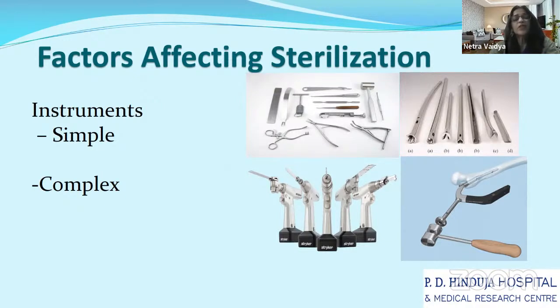Then you have your power instruments. How do you clean those power instruments? At the moment you have power instruments which can actually be soaked in water and detergent and cleaned properly, unlike the earlier ones wherein no soaking was allowed. The important thing to remember is to clean your instruments immediately with water and not with any other detergent, and absolutely no saline, because it is going to corrode your instruments and have a bad effect. For power instruments, you need to flush them immediately after use, clean them immediately, and then use the processes for sterilization.